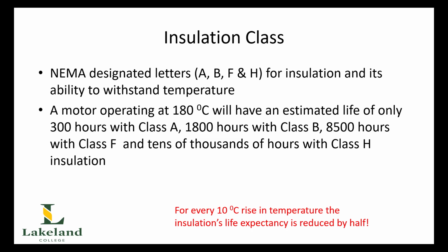So for example, a motor that's going to operate at 180 degrees is only going to last 300 hours if it was Class A insulation. However, if it was Class H insulation, it would last tens of thousands of hours. Now, electric motors are certainly not going to operate typically at 180 degrees. Outside or in typical indoor environments, they're going to typically operate around 40 to 50 degrees with the heat of the electrical current passing through them. But either way, Class H insulation is going to be the most heavy duty, will withstand the most amount of heat and therefore last the most amount of time.